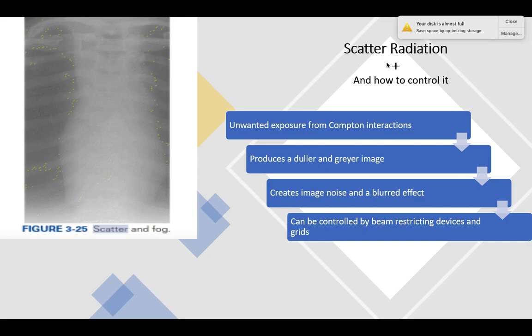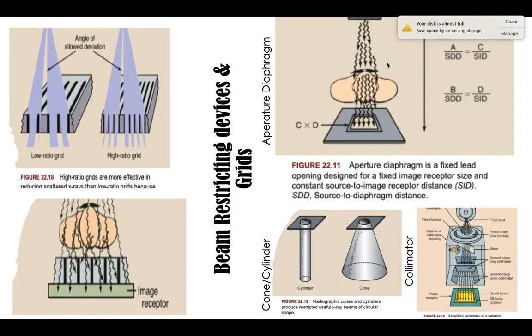Scatter can be controlled by beam restricting devices and grids. Beam restricting devices help to reduce the useful beam to the size needed. They limit the patient exposure and reduce the amount of scatter produced within the patient.